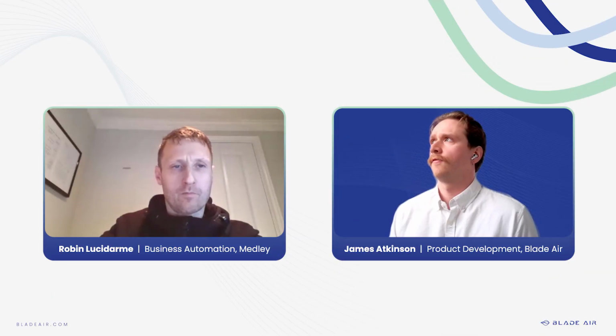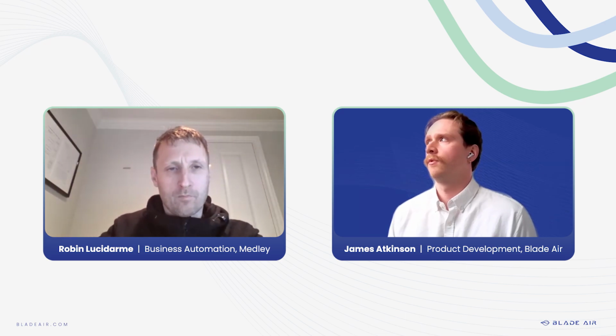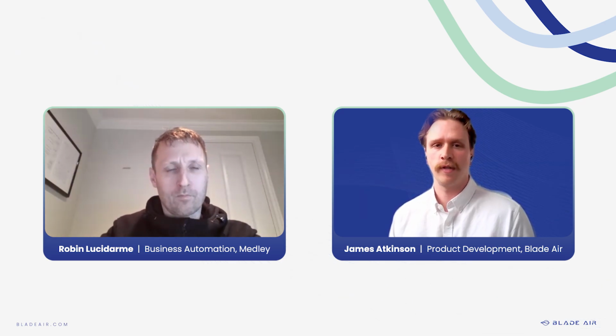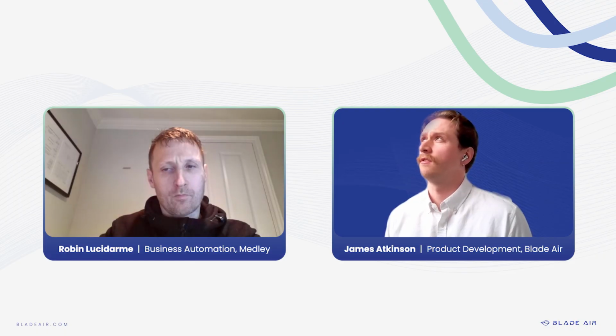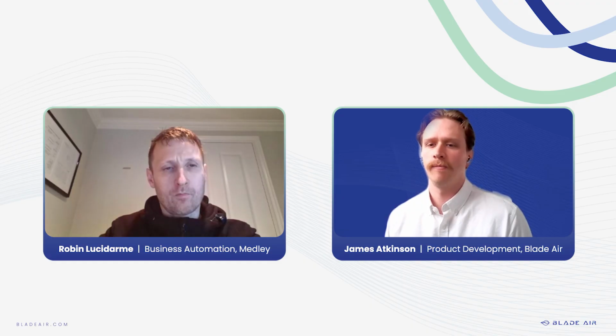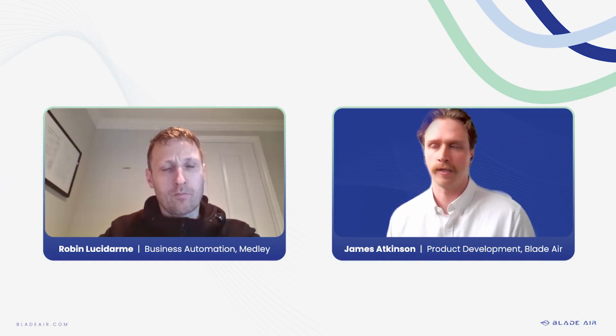Is there a maximum airflow rate where the Pro filter would not work? We test them to, I think it's 400 FPM standard. We wouldn't really want to go over 500, but that's a pretty conservative estimate. That's typical of most filters. It could be 492 FPM. It's the ASHRAE standard velocity that we test at. We don't like to go over 500 FPM. And if you need higher than that, we would recommend something else like a V-Bank, one of our other products that has stacked filters for higher airflow performance.